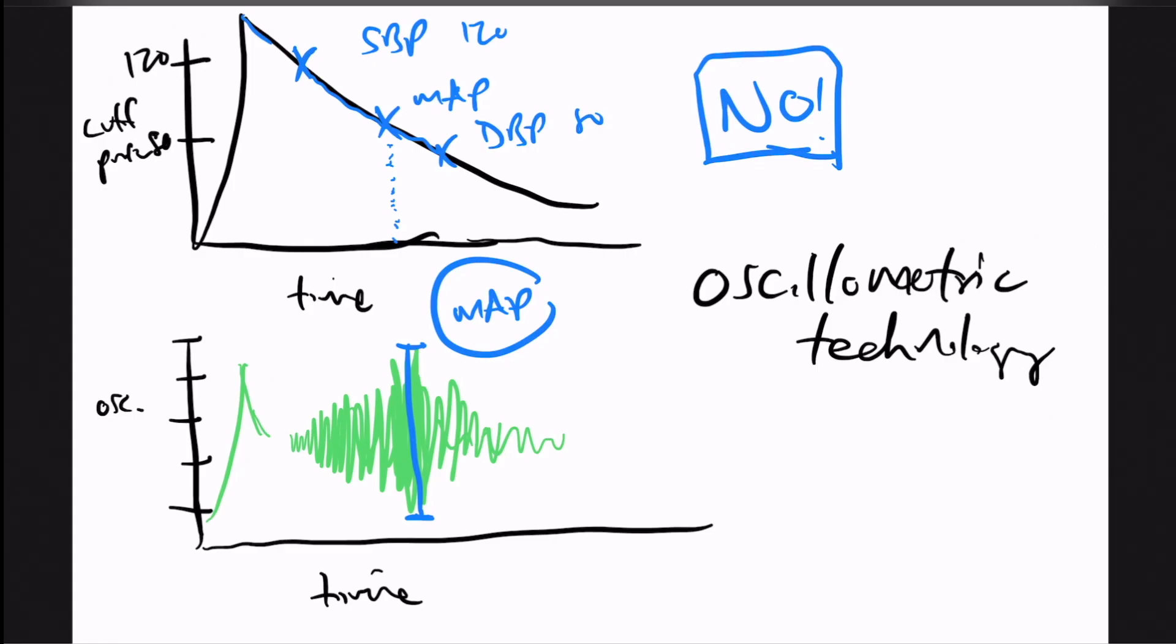This does correlate with the mean arterial pressure that's calculated when you do it via the manual technique. That's pretty cool, right? So the next question is, where in the world does the systolic blood pressure and the diastolic blood pressure come from? Each company that develops these technologies has their own proprietary software and their own proprietary code, which generates a diastolic blood pressure and generates a systolic blood pressure out of thin air, out of their code. That systolic blood pressure is not an exact number.